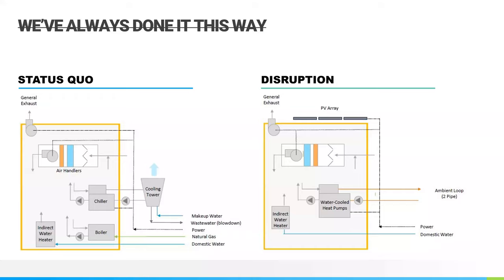So what they were doing here is instead having what they call an ambient loop. They say ambient because the water in that loop is roughly 75 to 85 degrees, so it's kind of an ambient neutral temperature. And that flows to each building on that campus. Within each building, there are water-cooled heat pumps that are providing hot water, chilled water, or air conditioning and heating for that building. So now it's all electrically powered heat pumps. They've got the PV array on top powering all the all-electric heat pumps that are providing the air conditioning, heating, and domestic hot water for the building. So you're no longer even having natural gas to the building.